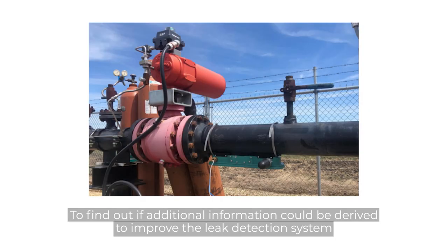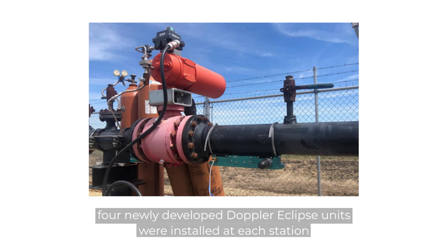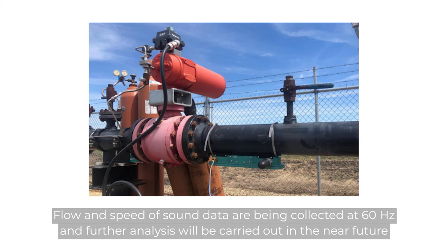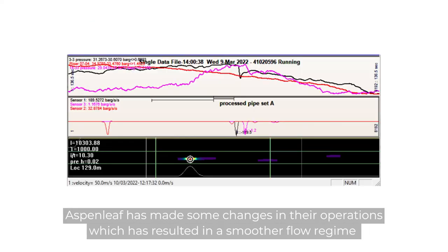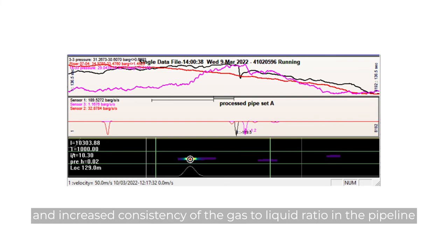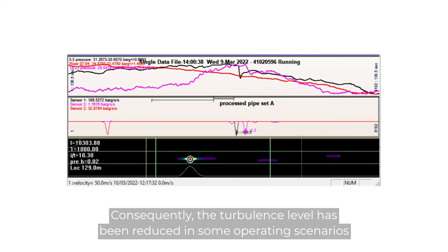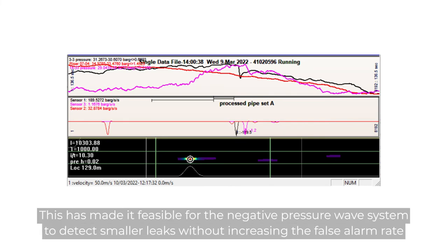To find out if additional information could be derived to improve the leak detection system, four newly developed Doppler Eclipse units were installed at each station. Flow and speed of sound data are being collected at 60 Hz and further analysis will be carried out in the near future. This photo shows the installation of an Atmos Doppler Eclipse at station 4. Aspen Leaf has made some changes in their operations, which has resulted in a smoother flow regime and increased consistency of the gas-to-liquid ratio. Consequently, the turbulence level has been reduced in some operating scenarios, making it feasible for the negative pressure wave system to detect smaller leaks without increasing the false alarm rate. This figure shows an example of a smaller leak being detected.